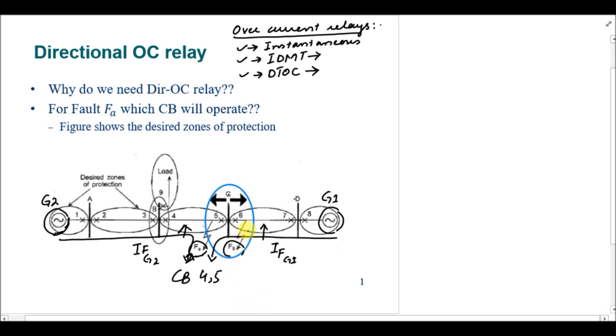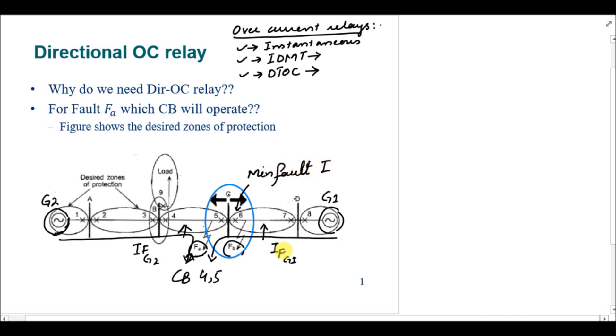However, circuit breaker six can also operate because it is close to the point where the fault is occurring. There is a chance that the fault current passing through circuit breaker six will be greater than the minimum fault current of that relay's setting. So due to IFG1, circuit breaker six may also operate undesirably.